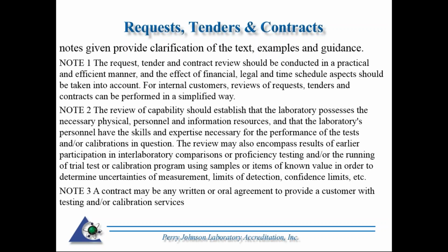The review may also encompass results of earlier participation in interlaboratory comparisons or proficiency testing and or running a trial test or calibration program using samples or items of known value in order to determine uncertainty of measurements, limits of detection, confidence limits, etc. Oftentimes those avenues, interlaboratory comparison, repeatability studies, intralab studies can actually be utilized as quantifiable components into the uncertainty of the testing in our calibration lab.